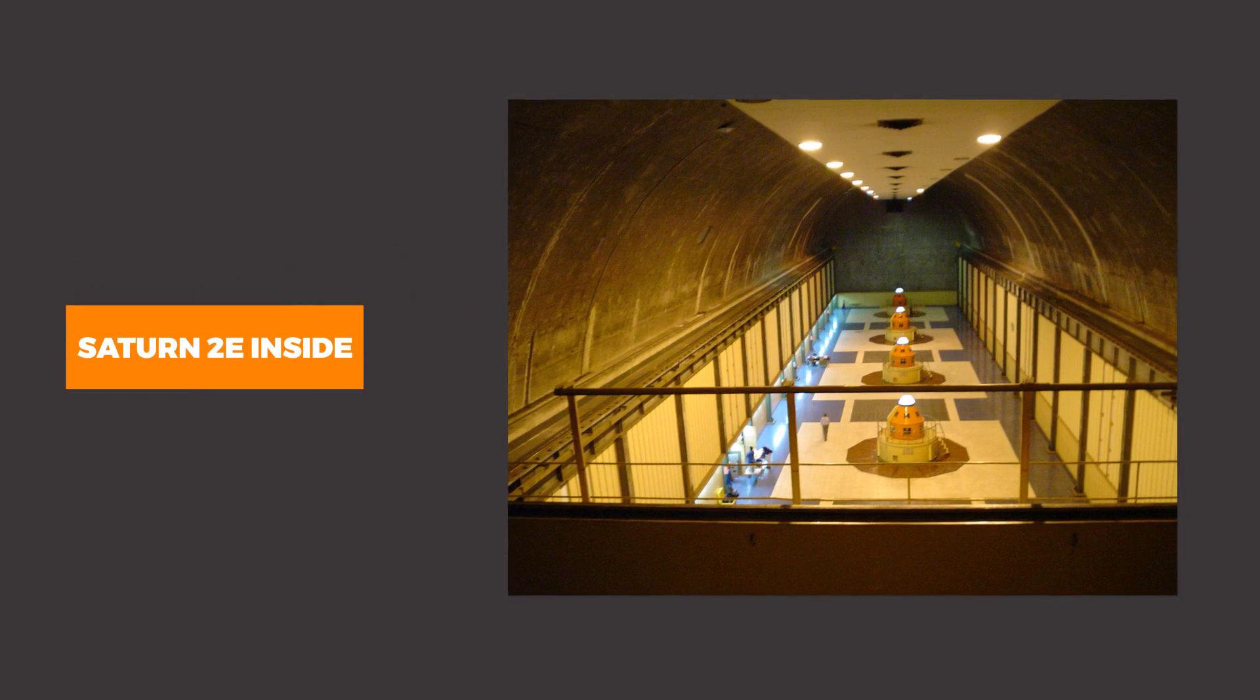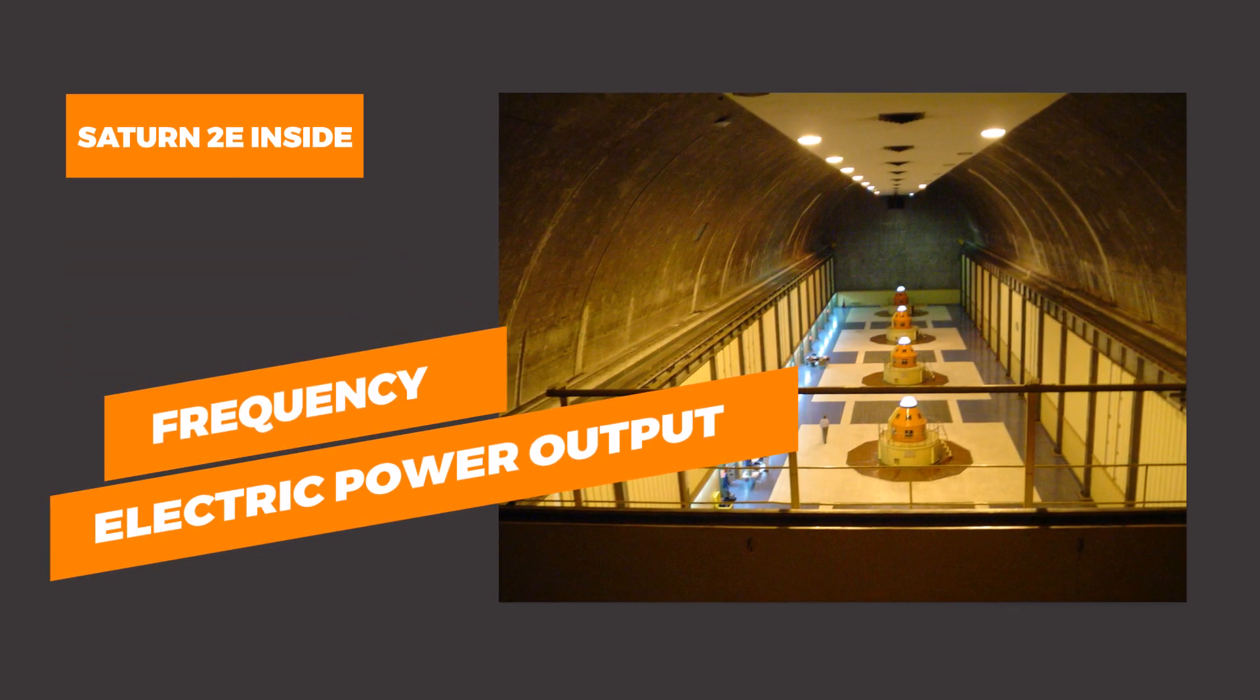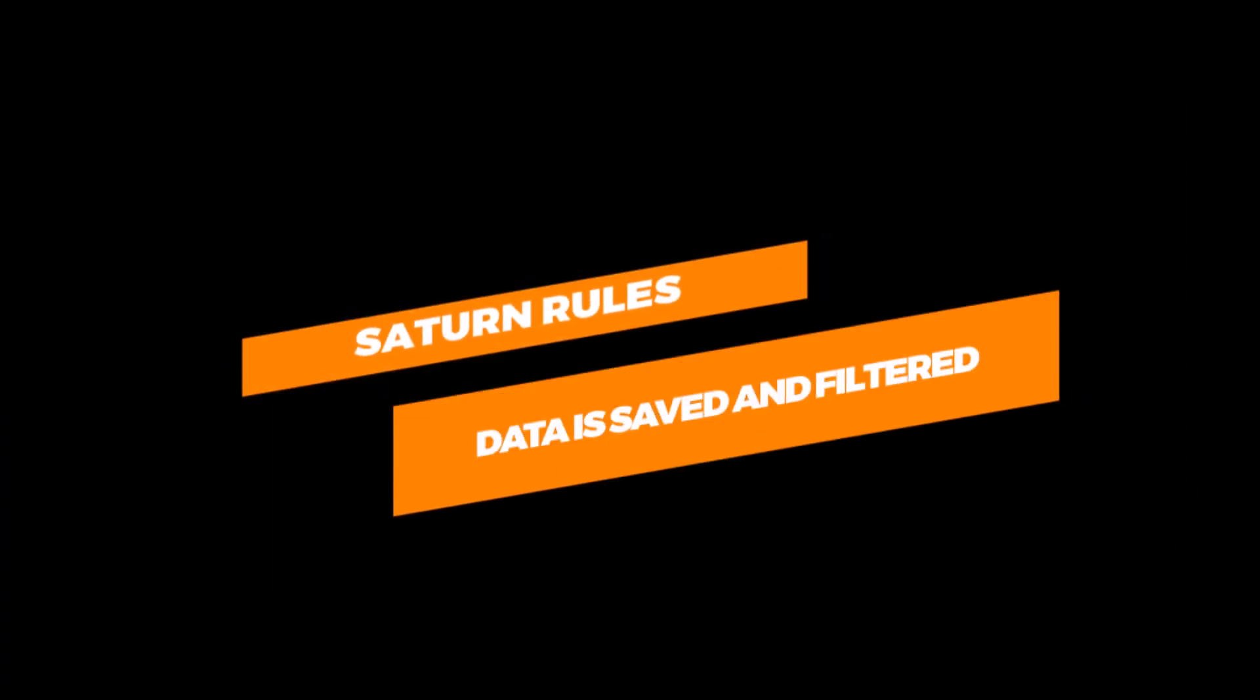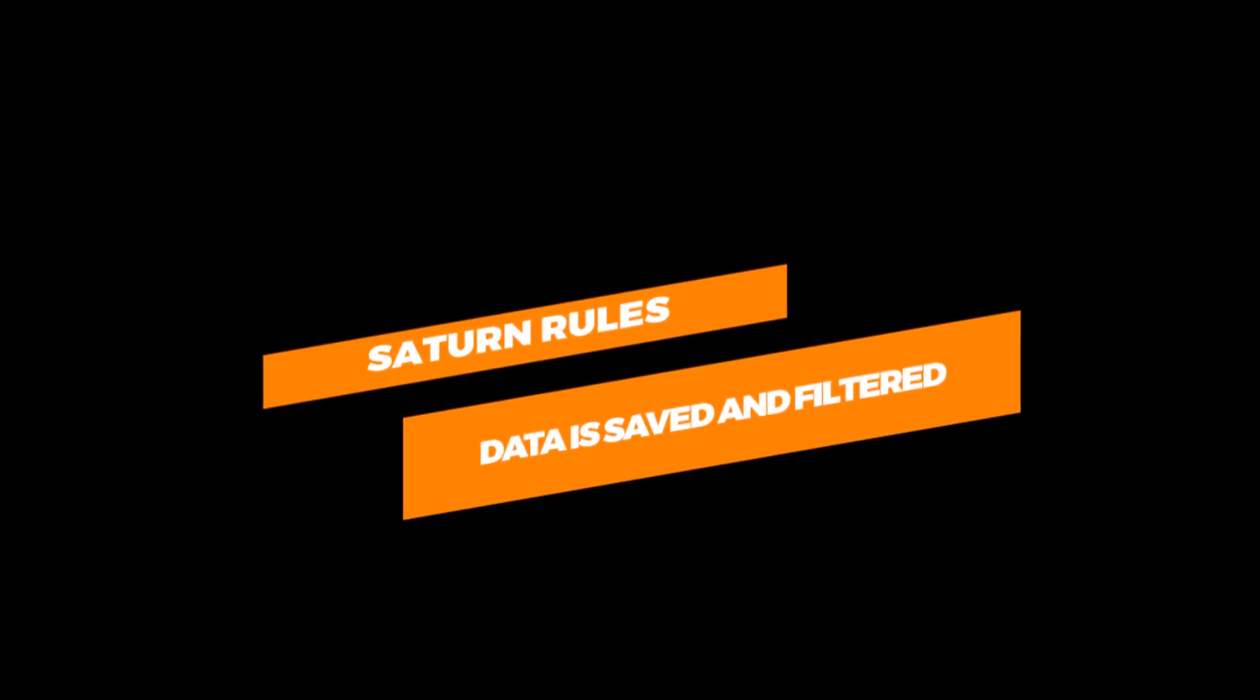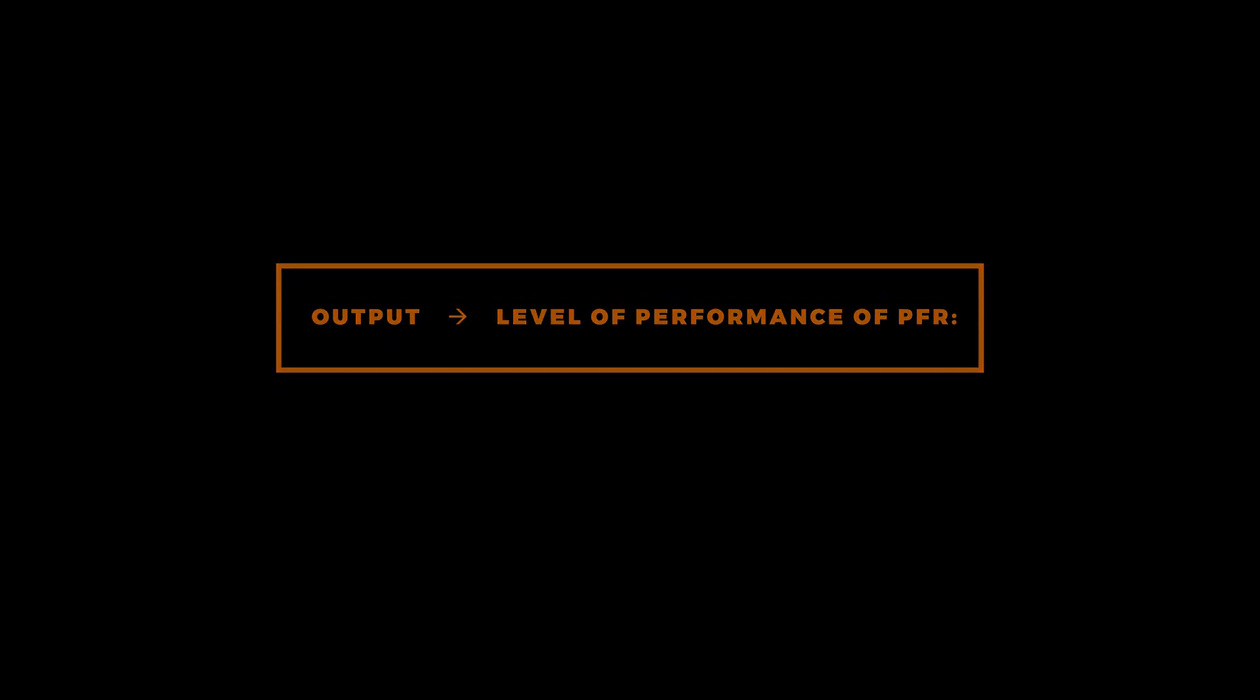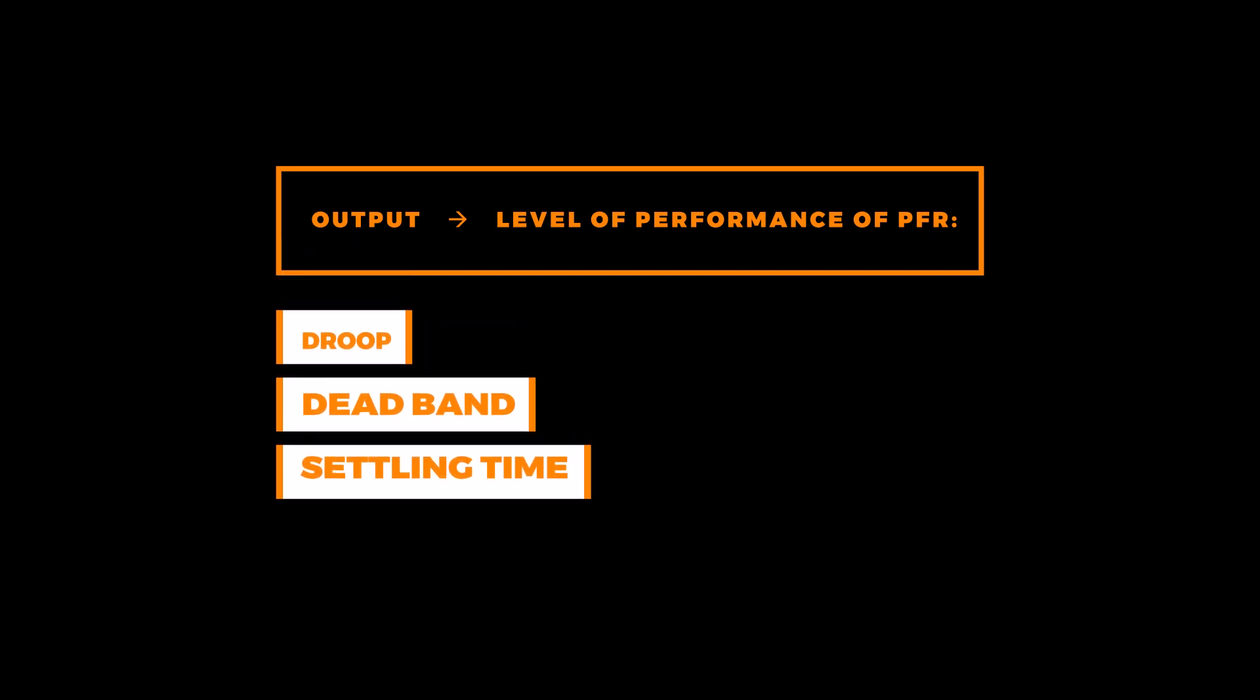Saturn 2E is constantly monitoring frequency and electric power outputs of the generator units. Data is saved, filtered, and processed within Saturn's rules, which are designed based on each country's grid codes. The output of the algorithm is the level of performance of the frequency regulation and is determined by the following parameters: Droop, deadband, and settling time.